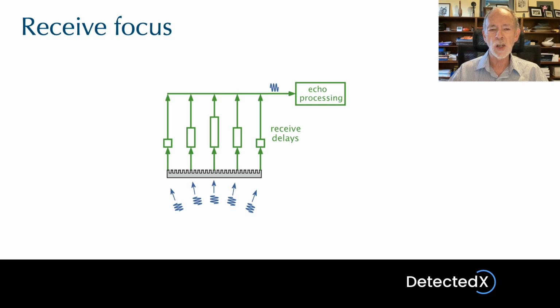So the machine is constantly adjusting and readjusting the receive focusing function to accommodate the fact that the echoes will be coming from progressively greater depths as the microseconds pass. So as time passes, the machine is constantly readjusting the focus, so it's always tracking the depth from which the echoes are coming. So the receive focus is perfect at all depths. The transmit focus is not, because once the transmit pulse has been launched into the tissues, the machine has no further control over it, and so it can only focus at one depth, as I've already discussed. So the transmit focus is at one depth, and that's what the user adjusts on the screen. The receive focus is automatically dynamically swept so that it is always optimum.